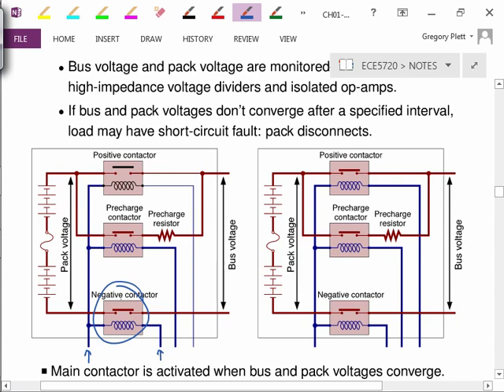We want to apply power to the positive terminal of the load in a way that limits the current flowing to charge up the load's capacitance. That's where the pre-charge resistor comes in. When we power up the pre-charge contactor, both sides of the coil are powered, closing that switch.